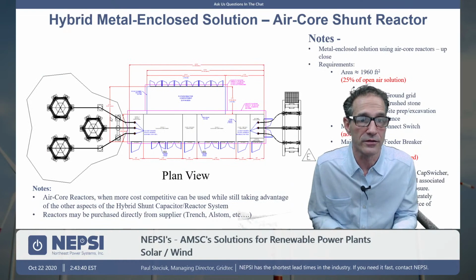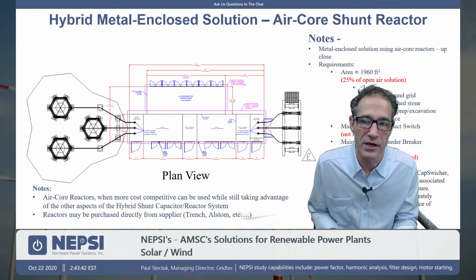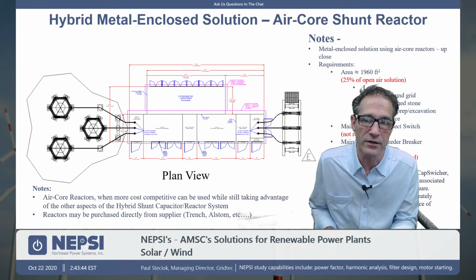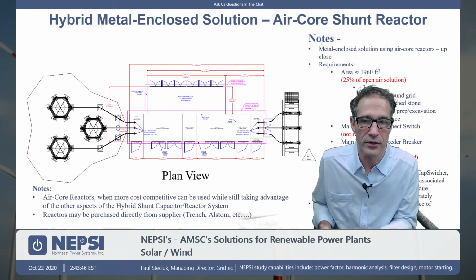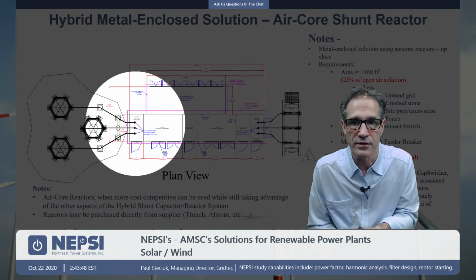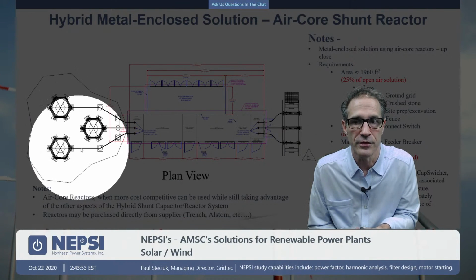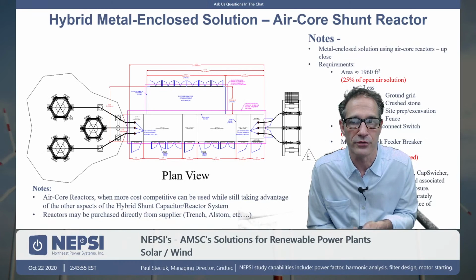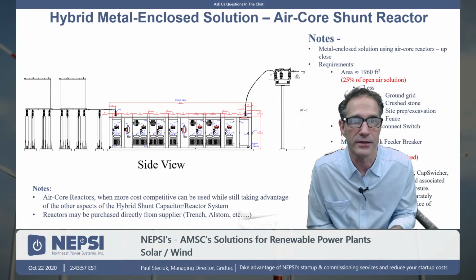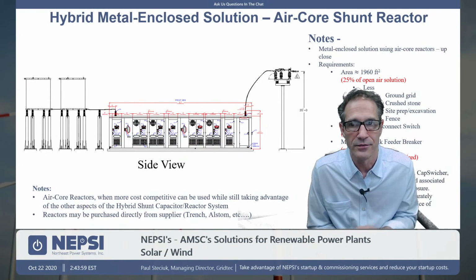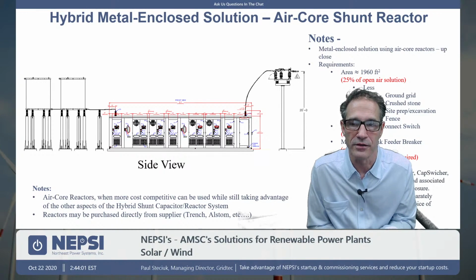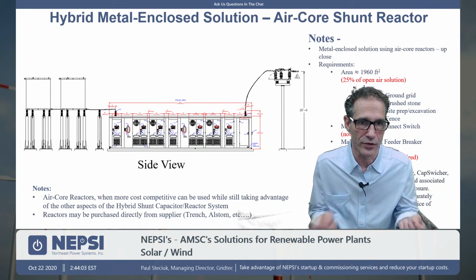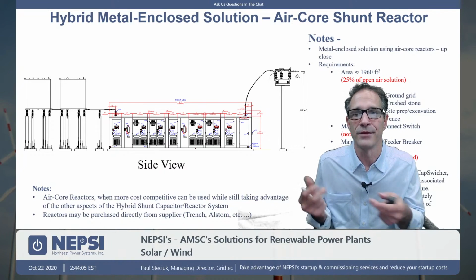So if you're trying to keep the project as competitive as possible, you could go to Trench or Phoenix and buy the air core reactors separately. We'll still put the switching device inside our enclosure, but put roof bushings in, and then you can purchase their air core reactors by themselves. So as you get up into that 10 or 20 megavar range, maybe the iron core reactor is not competitive from a price standpoint.